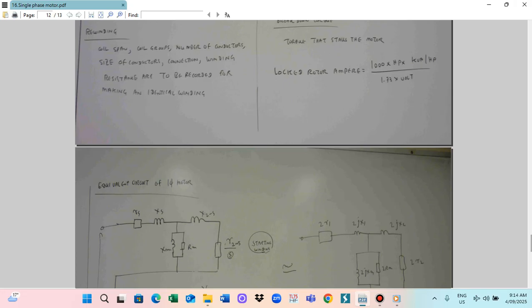So this covers the important characteristics of the single-phase and the 3-phase motor, the abnormal operating conditions, the differentiation, and also the maintenance. Now I can also talk about the torque and the horsepower of the single-phase induction motor. This is the equation to calculate for the motor. So motor horsepower can be calculated.